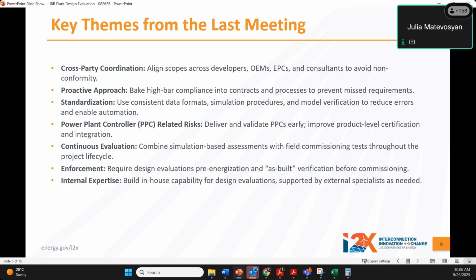Require design evaluation, pre-energization, and as-built verification before commissioning if you want to verify that the plant conforms with applicable requirements during the interconnection process, not after the fact. There's also a need for internal expertise. Rishi talked about how many consultants are involved, each understanding only a certain portion of the project design, and there's value in having in-house design evaluation capability supported by external consultants.